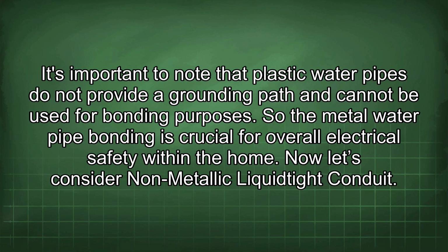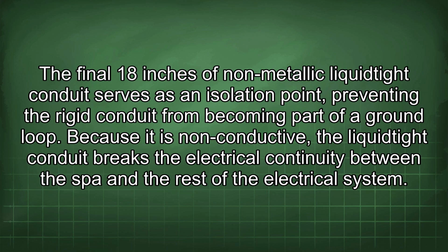Now let's consider non-metallic liquid-tight conduit. The final 18 inches of non-metallic liquid-tight conduit serves as an isolation point, preventing the rigid conduit from becoming part of a ground loop. Because it is non-conductive, the liquid-tight conduit breaks the electrical continuity between the spa and the rest of the electrical system.